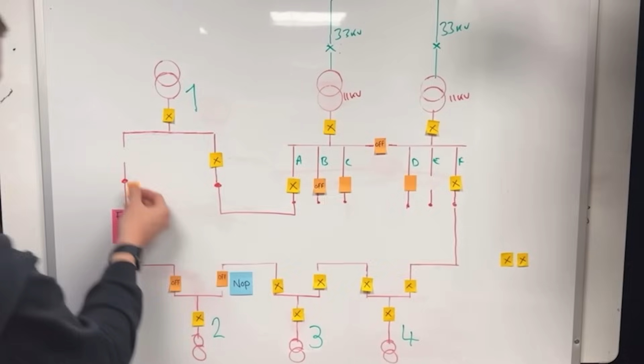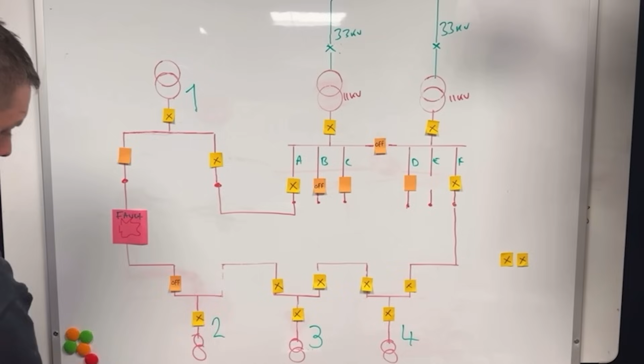Then we'd be able to re-energise that, which would get them on. And then we have to move that normal point - it would stay there, but we'd get rid of it temporarily and put that one on. That's right, innit? Now everyone's got power, and the damaged section is isolated. So that's how the ring main becomes really flexible and enables you to switch people on and off or move normal open points around to cater for faults and maintenance at different times.